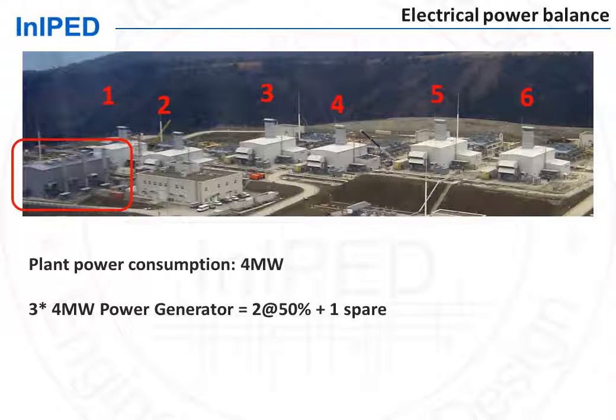This allows to size the plant power generators. As uninterrupted power is required, there are several generators in order to have backup — if one fails, the other generators can compensate and take up the load. For instance, if the total power consumption of the plant is four megawatt, three generators each of four megawatt capacity would be a suitable selection. Two generators will operate at 50% capacity and one would be spare. If one generator fails, the other one that is already running will be able to go to 100% and take all the load of the plant.